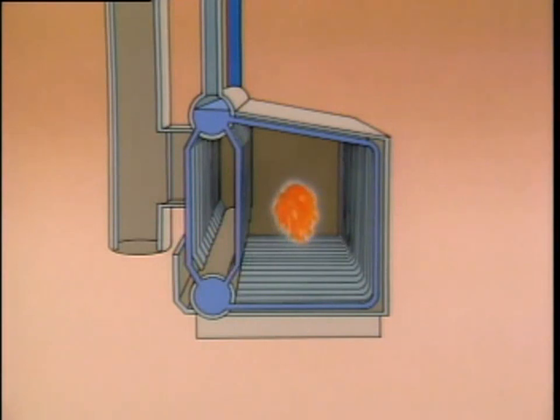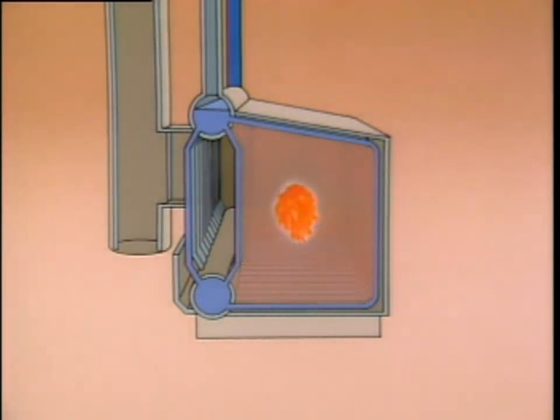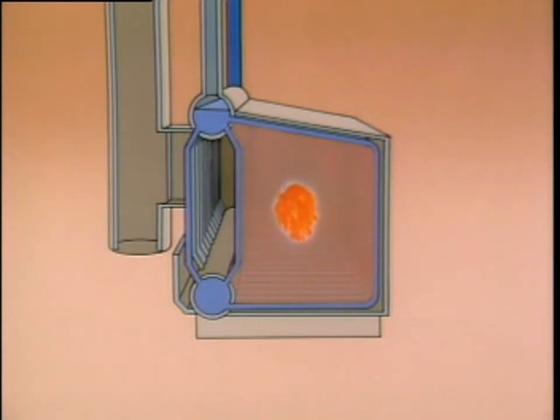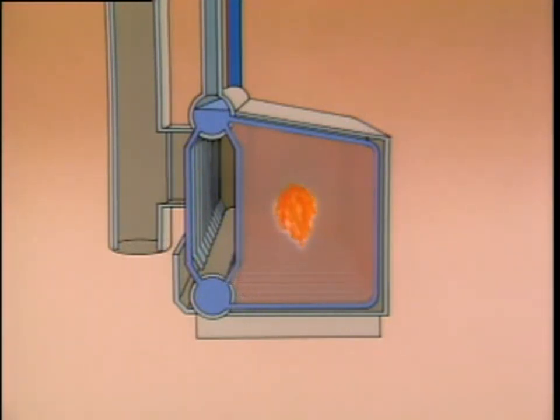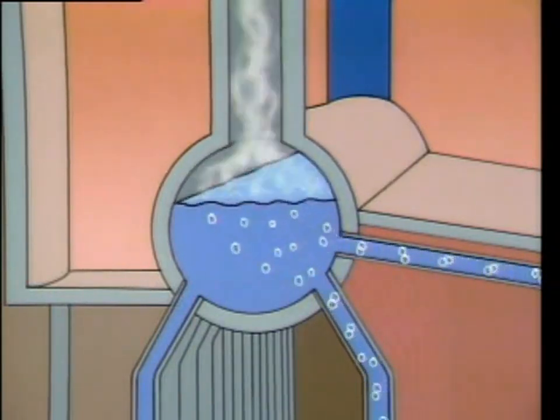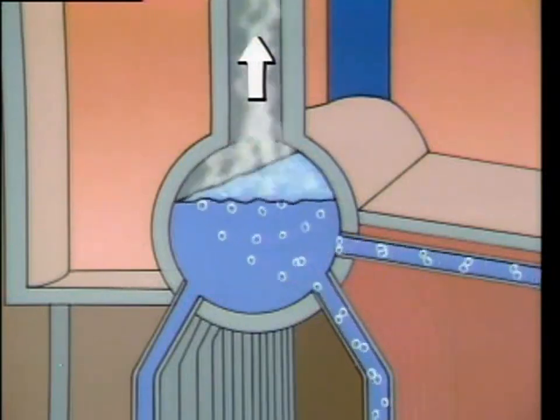As fuel is burned in the combustion area, heat is transferred to the adjacent water tubes. The combustion gases then flow out of the boiler. Water circulates from the upper drum through the water tubes and into the lower drum, which is often referred to as the mud drum. From the lower drum, the water is distributed to the water tubes surrounding the combustion area. As the water in the tubes is heated, a steam-water mixture is produced. The steam-water mixture enters the upper drum, where the steam is separated from the water and routed through the steam outlet and into the plant.